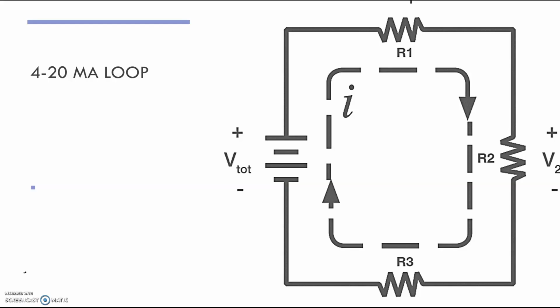So this is the dominant type of analog signal used in process control, and it's based on fundamental principles like Ohm's law, where the current is constant in a loop. And it's got some characteristics that we'll look at. It's very well standardized. So that 4 milliamps means 0% output and 20 milliamps means 100% output. So it's easy to detect issues.